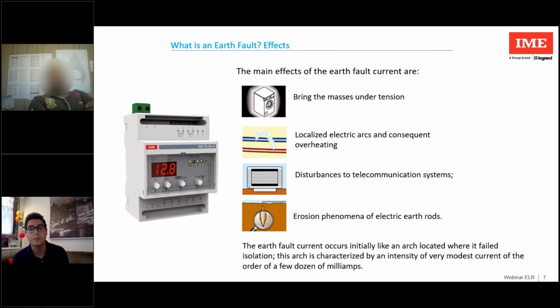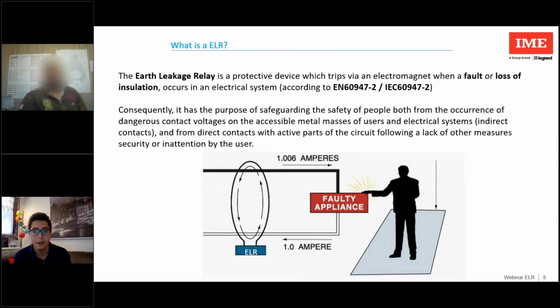First of all, it can bring the masses under voltage or generate electric arcs and consequently overheating, disturbance in the telecommunication system, or a possible erosion of the electric earth rod. So a real problem for people and objects. Well, what can help us to prevent these events? Here the earth leakage relay comes to our help.